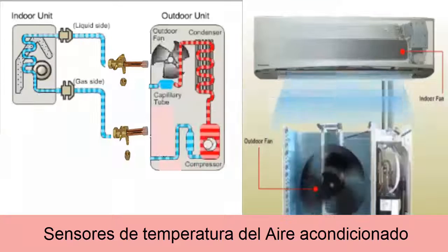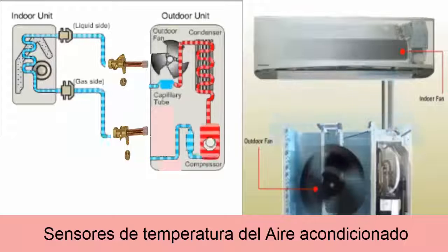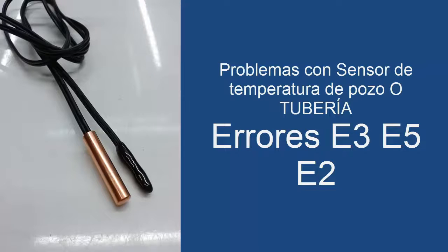We can also have the well sensor, which is responsible for verifying that there is no freezing of the evaporator. When there are problems with this sensor, we will find the codes E3, E5, and E2.